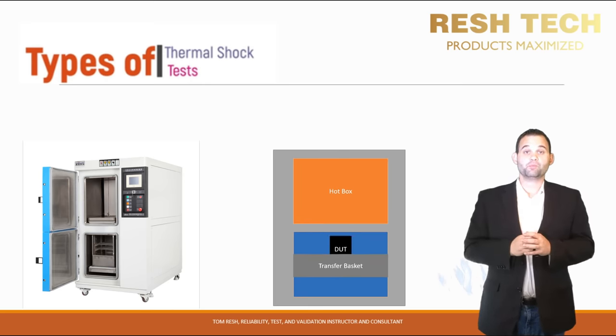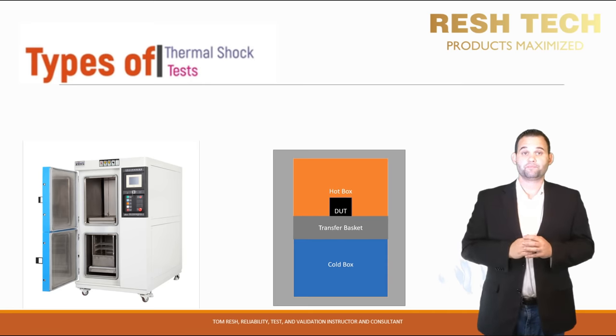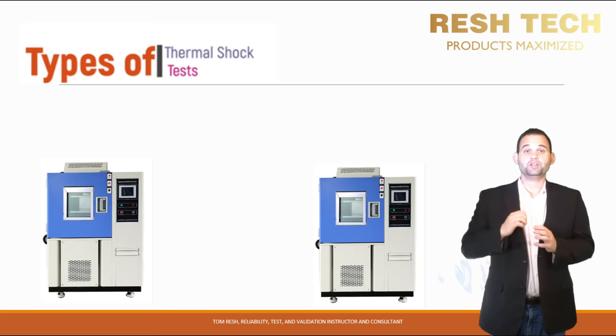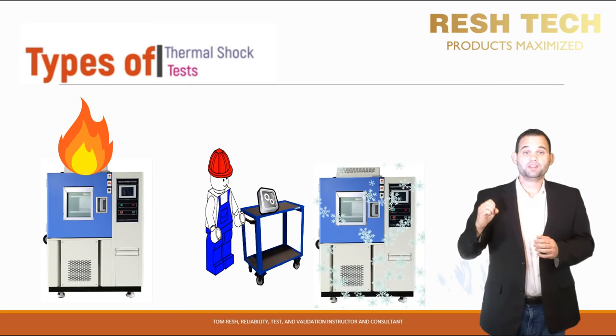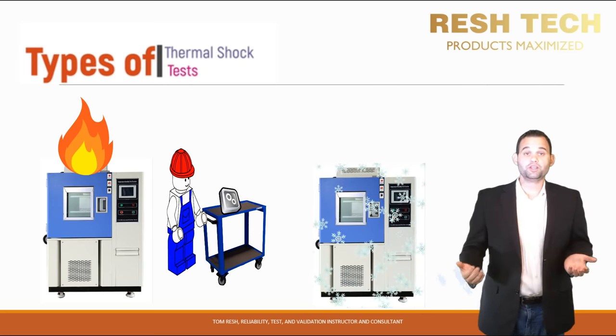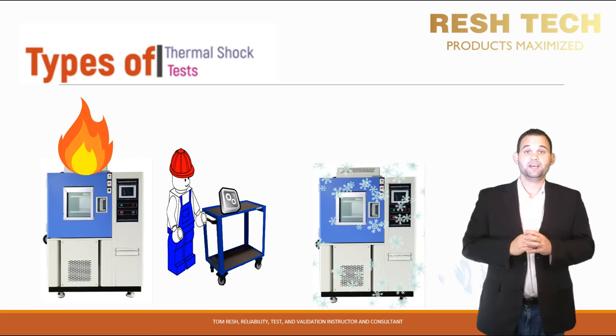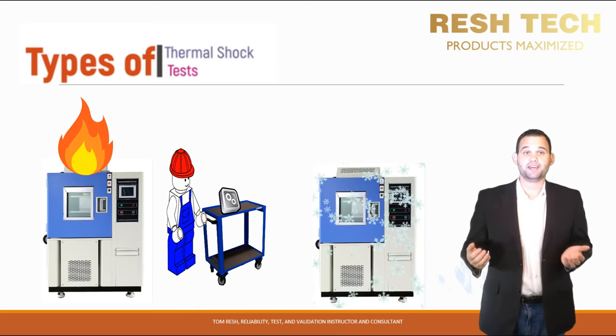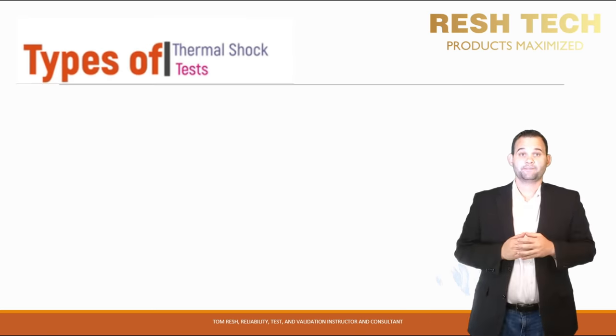Thermal shock chambers are more expensive than traditional temperature test chambers and, depending on the size of the part or system you are testing, can be very expensive. Another solution is to use two temperature test chambers — condition one to your hot temperature set point and the other to your cold temperature set point — and then manually transfer your part or system between the two after a specified soak period. The downside is you will need to run multiple shifts with technicians or engineers on day and night shifts depending on your soak periods and number of cycles.